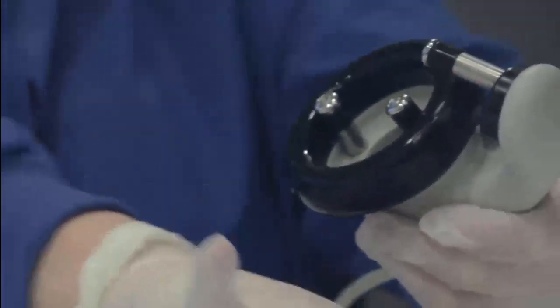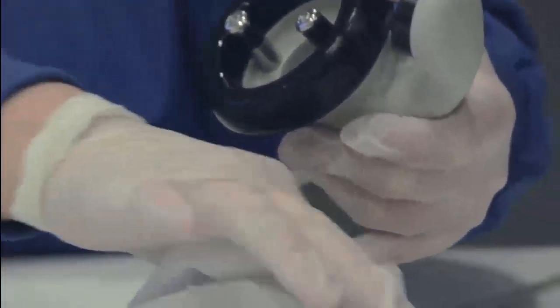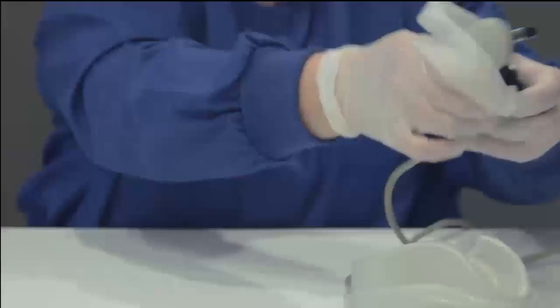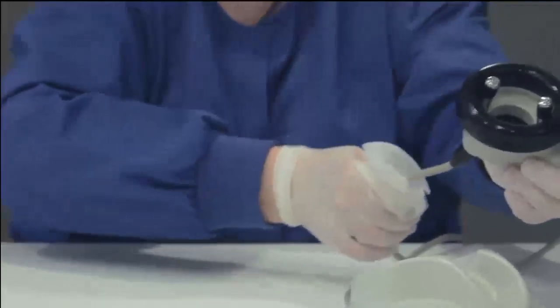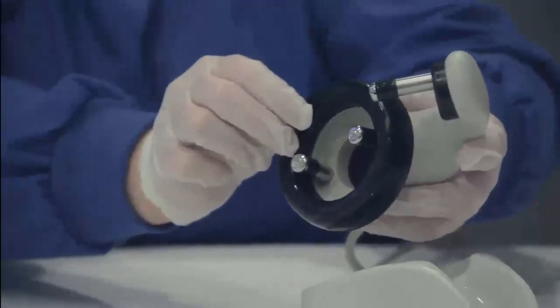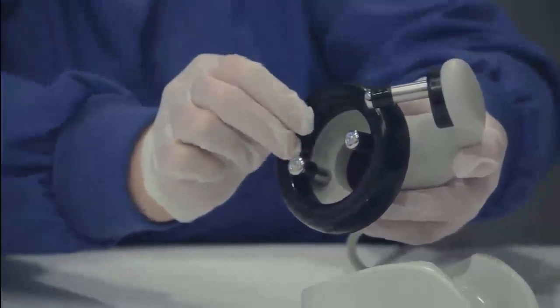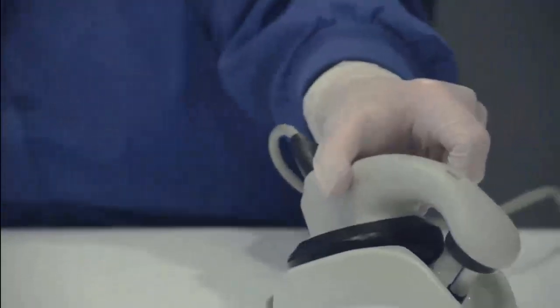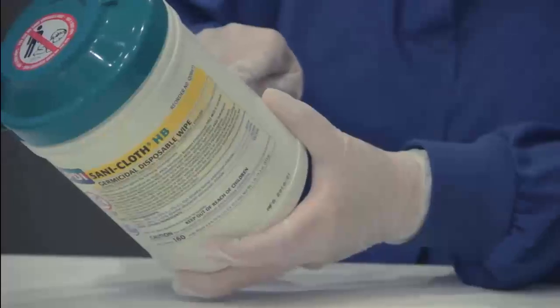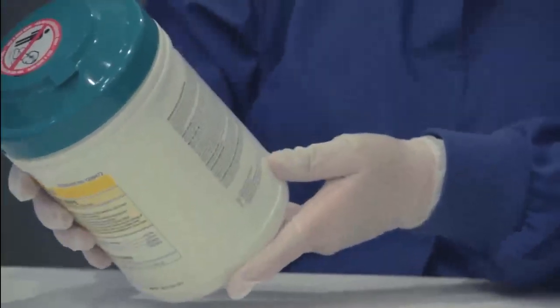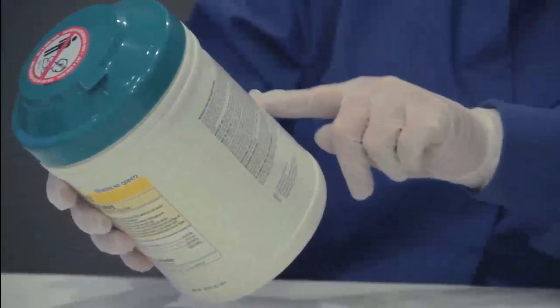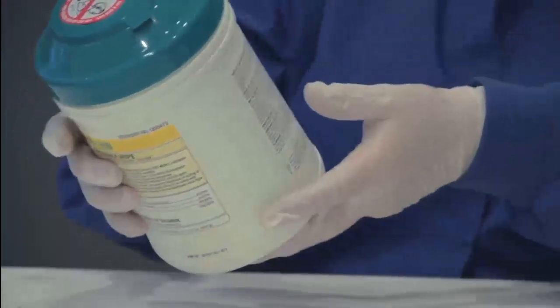Disinfect the electrodes, ear cushion, cable, and other components that made contact with the baby or the baby's bedding by wiping them with a fresh disinfectant wipe. Use of a non-alcohol-based disinfectant product is recommended. If an alcohol-based disinfectant is used, the ear cushion material will be affected over time, causing it to harden and crack. It will need to be replaced more frequently. Be sure to follow the directions for use and handling precautions on the disinfectant product. Allow the disinfectant to dry thoroughly according to the manufacturer's recommendations before using the BERAphone on the baby.